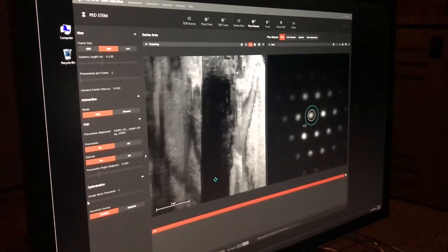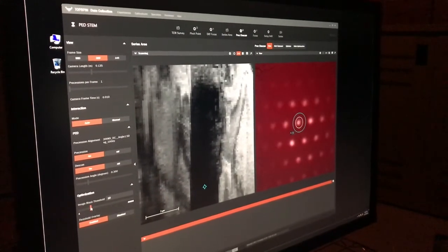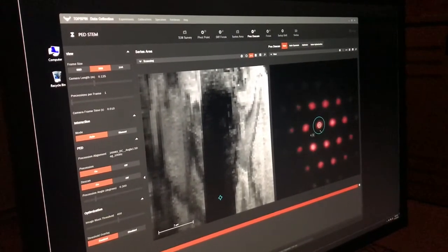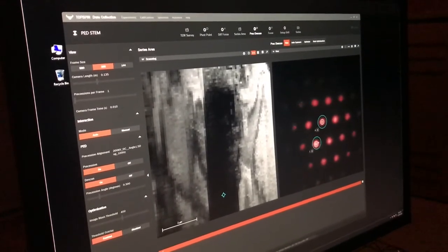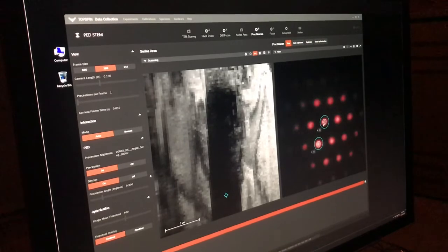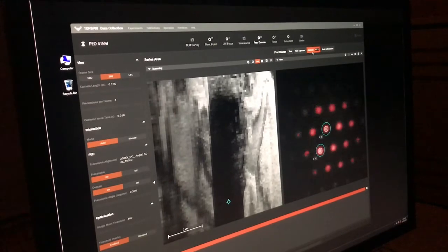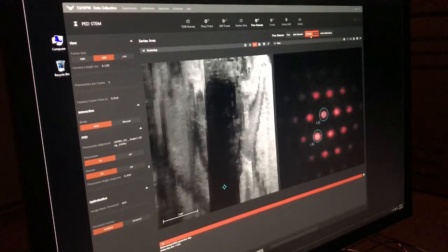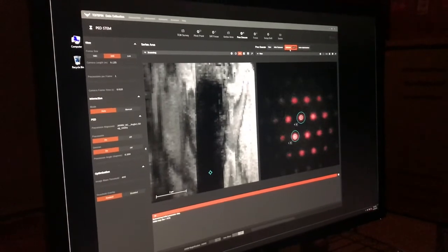Under the optimization menu, you can apply mask. By increasing the number, the diffraction spots will show up. Resize the blue circle. Then left click on one diffracted spot and resize and center the blue circle again. Click on optimize. The idea of optimization is to make those spots as small as possible. When you don't see any changes, manually stop it.